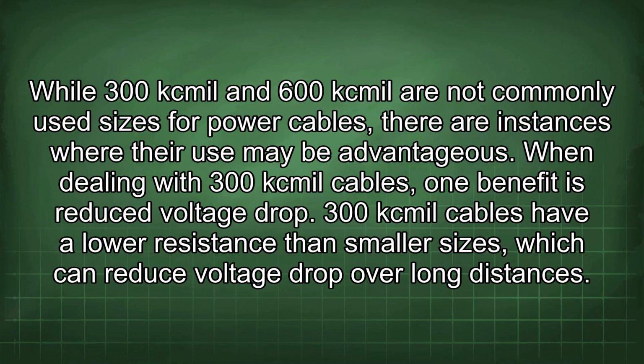While 300kcmil and 600kcmil are not commonly used sizes for power cables, there are instances where their use may be advantageous. When dealing with 300kcmil cables, one benefit is reduced voltage drop. 300kcmil cables have a lower resistance than smaller sizes, which can reduce voltage drop over long distances.